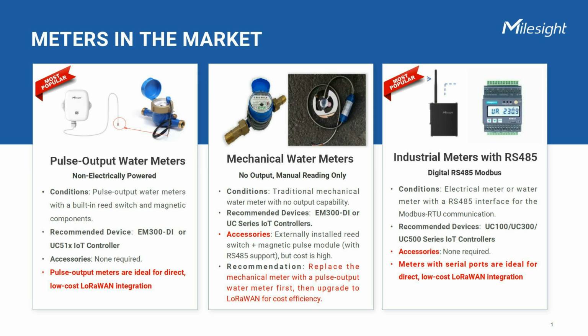And finally, for industrial meters with RS485. If your fancy meters already speak Modbus over RS485, you're in luck. Plug and play with UC100, 300, or 500 controllers. They grab data via Modbus and shoot it over LoRaWAN. Zero extra parts, instant smart meter.